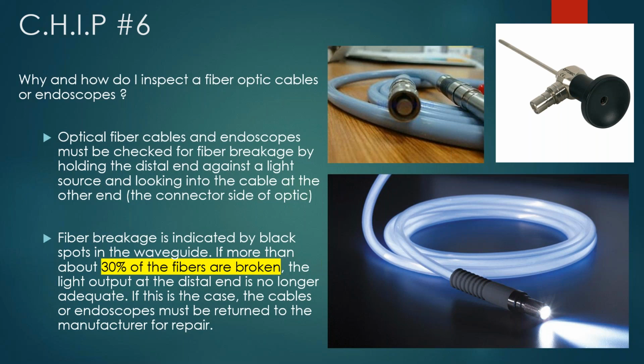A lot of times it can be just held up to the light. I do not suggest plugging it into a light source because those actually produce quite a bit of light and you really don't need that much. So just holding it up to the light over your workstation can actually produce enough to look through and look for broken fibers. And fiber breakage is indicated by little black spots as you look through.